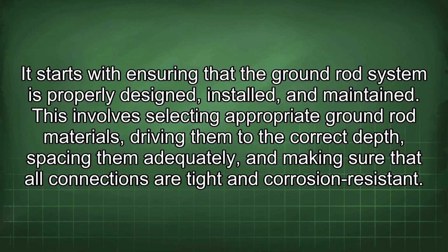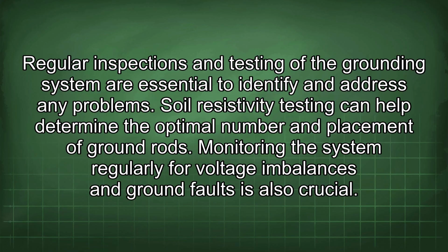It starts with ensuring that the ground rod system is properly designed, installed, and maintained. This involves selecting appropriate ground rod materials, driving them to the correct depth, spacing them adequately, and making sure that all connections are tight and corrosion resistant. Regular inspections and testing of the grounding system are essential to identify and address any problems. Soil resistivity testing can help determine the optimal number and placement of ground rods.